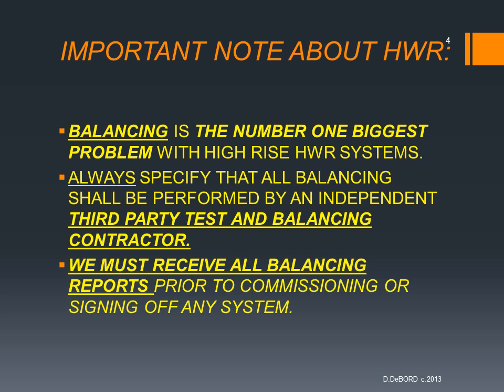It's important to note that balancing is absolutely the number one biggest problem with high-rise hot water return systems. Always specify that all balancing shall be performed by an independent third-party test and balancing contractor. Then make sure that you receive all the balancing reports. Make sure they're valid, they're for the building you're looking at, they weren't all copied from one another, and that they didn't just make the stuff up. And we need to do this before we sign off on anything, and that includes the punch list, and that includes commissioning.